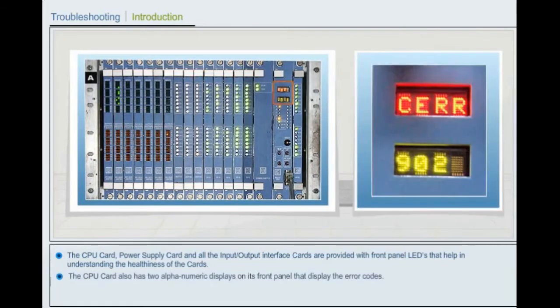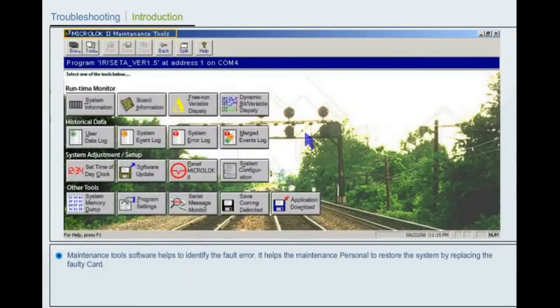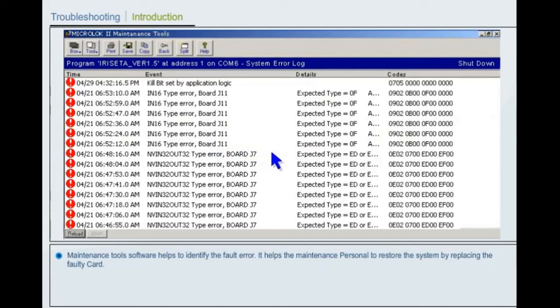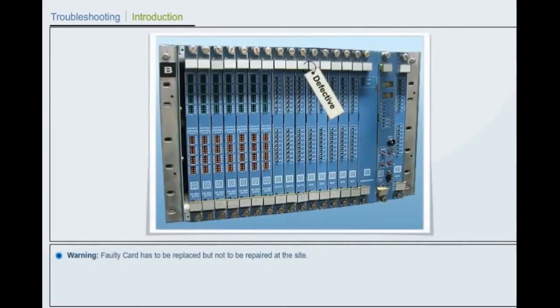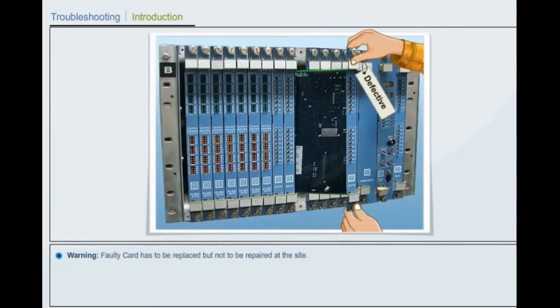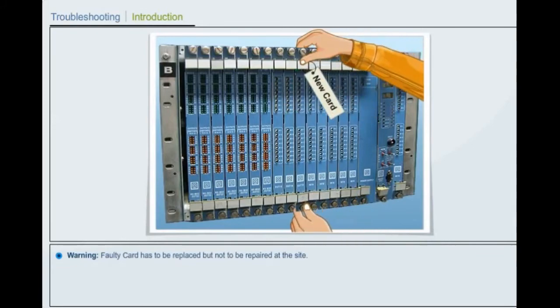The central processing unit card also has two alphanumeric displays on its front panel that display the error codes. Maintenance Tools software helps to identify the fault error. It helps the maintenance personnel to restore the system by replacing the faulty card. Warning: faulty card has to be replaced, but not to be repaired at the site.